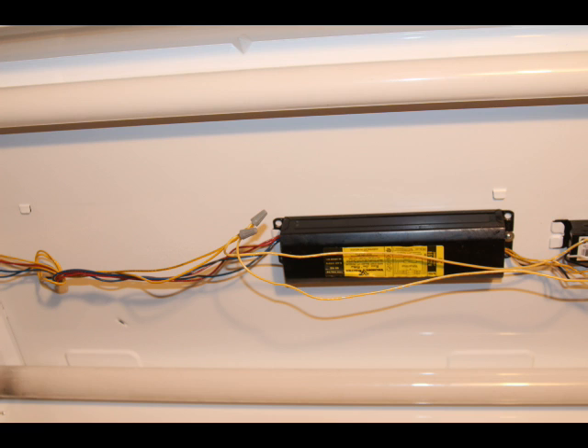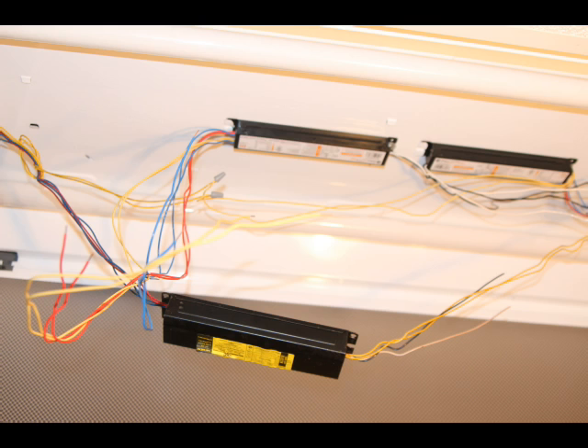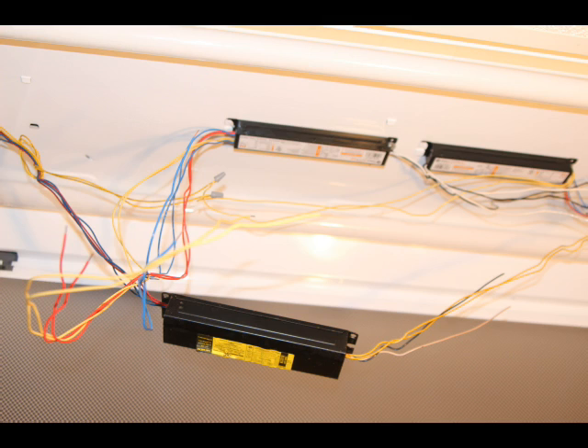Now we're on to the replacement of the second ballast. Now, two of my fluorescent tubes were operating properly, so it's quite conceivable that I could have replaced only one of these ballasts and made my fix. However, as I went to a new style of electronic ballast, and there might be some quick start and possibly some economical advantages, I elected to replace both ballasts.